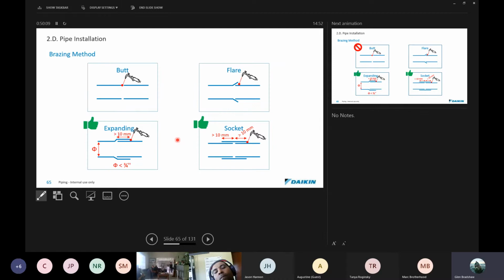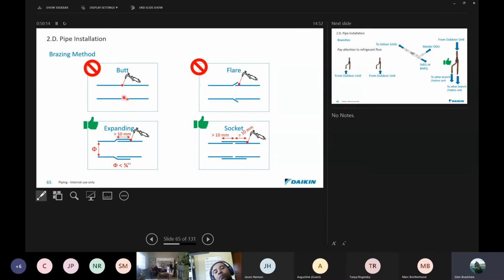Joining methods that are not acceptable. You may not butt join. You cannot just push two pieces of pipe together and weld them. You cannot flare a pipe and weld it either. You may use a swage joint or a socket only, when joining two sections of piping together.